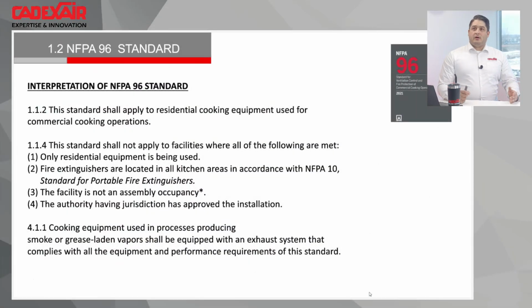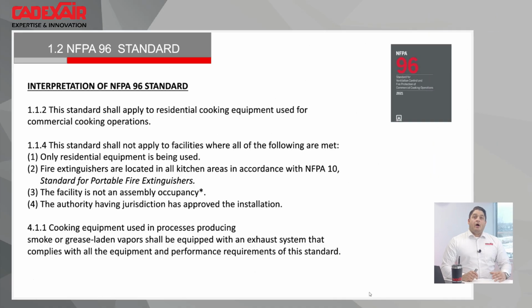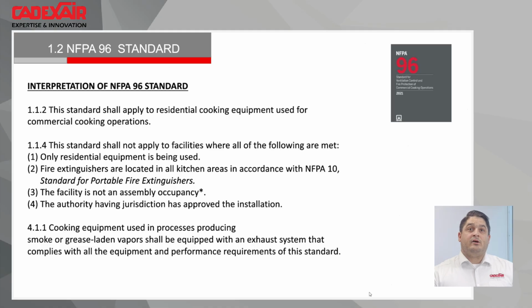After that, now we have checked our project, and we have determined, okay, we need to comply with NFPA 96. So just to double check, when you look in NFPA 96, what are they also thinking about regarding the use of residential equipment or things like that. So technically, this standard, NFPA 96, shall apply to residential cooking equipment used for commercial cooking operations. So as soon as you have a commercial cooking operation as per NFPA 96, you should have a full commercial kitchen exhaust hood system. And that's a good example: if you have a restaurant and you put 4 residential electric ranges side by side, you will need to comply with NFPA 96.